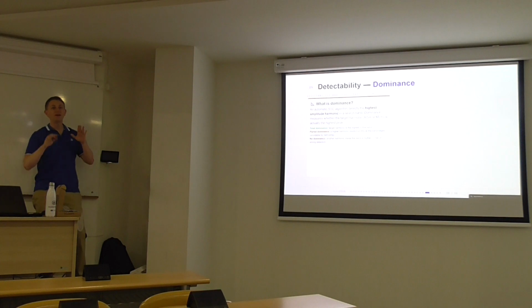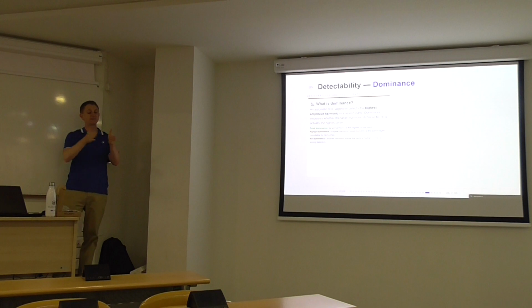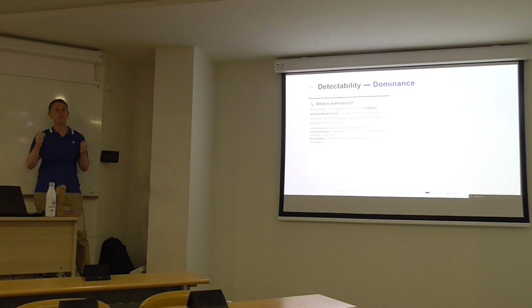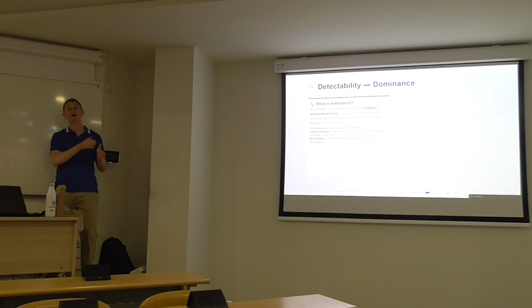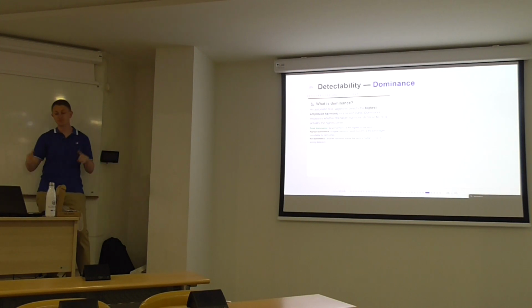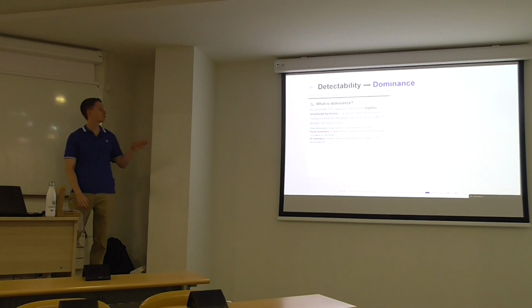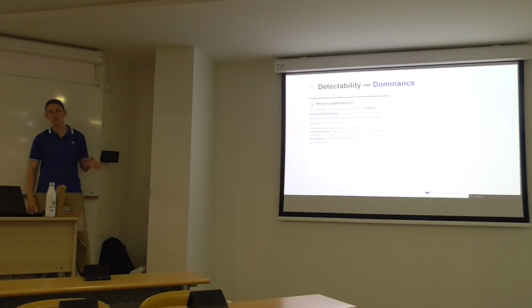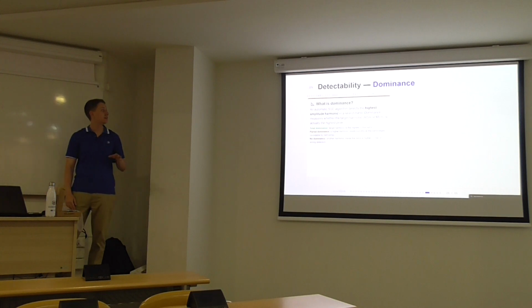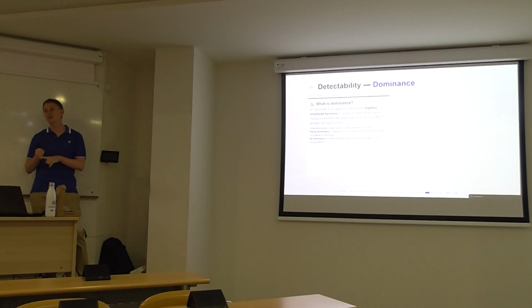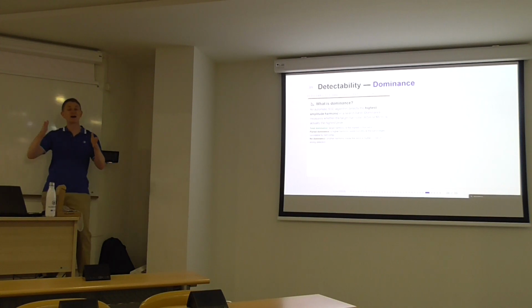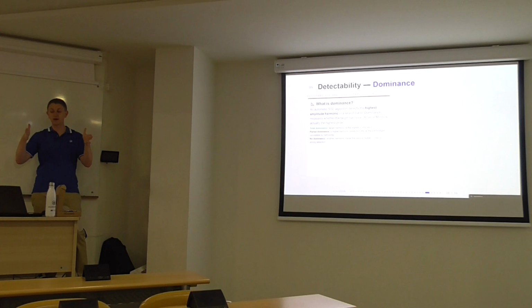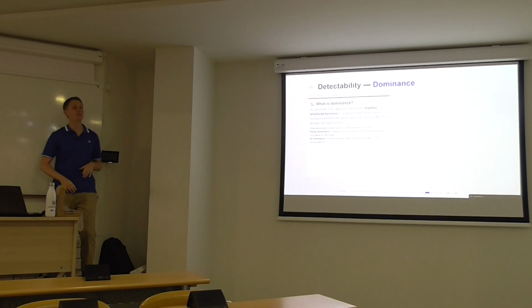So, for you to know, in any automatic sensorless speed estimation algorithm, we detect the highest peak in a slip band. That slip band is defined by the slip at no load, that is zero slip, and the slip at rated load. So that is the slip band. Dominance measures whether the target harmonic, rotor load harmonic or mixed eccentricity harmonic, is actually the highest peak. Total dominance means it is the highest. Partial dominance means a higher harmonic exists, but it is at the edges of the band, so we can narrow the band and avoid it. And then no dominance.